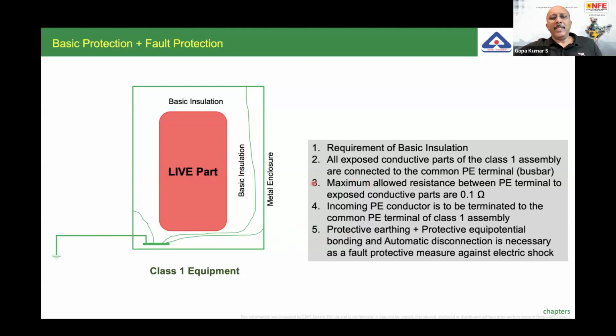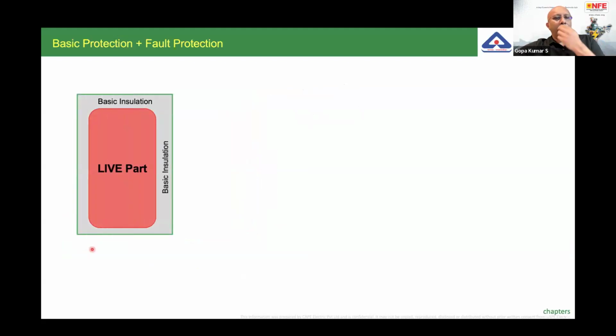So basically, serial number 1 to 4 is about the equipment. Serial number 5 is, once you buy a class 1 equipment, your building should have protective earthing, protective equipotential bonding, and automatic disconnection of supply as a fault protective measure for a class 1 equipment. Similarly, on equipment you can see the numbering, the symbol for protective earthing, the earthing symbol with a circle, or 5019, which is a number that can be given for this particular application, or green and yellow.